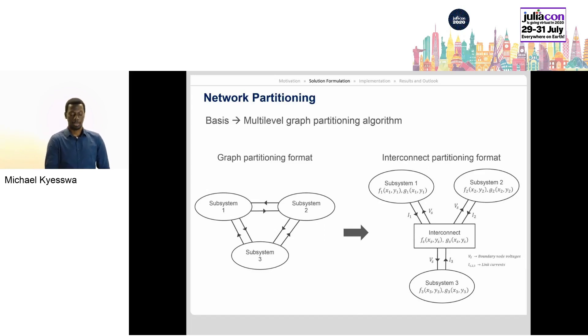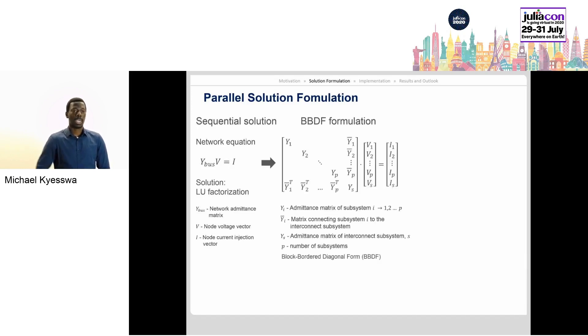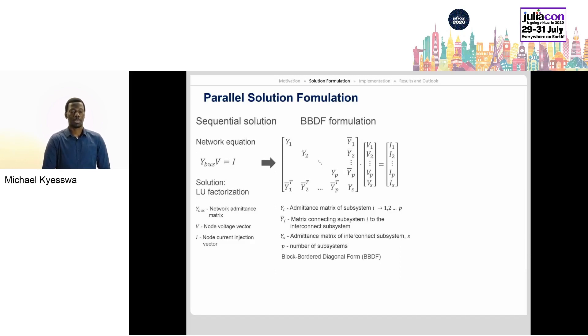Once the subsystems are formed, the network equation can then be reformulated from a current balance form with an admittance matrix for the whole network into a bordered block diagonal form, consisting of admittance matrices for the different subsystems and an admittance matrix for the interconnecting subsystem.